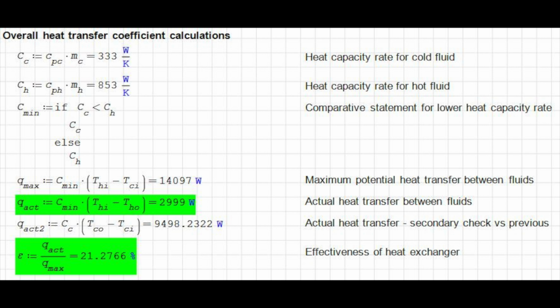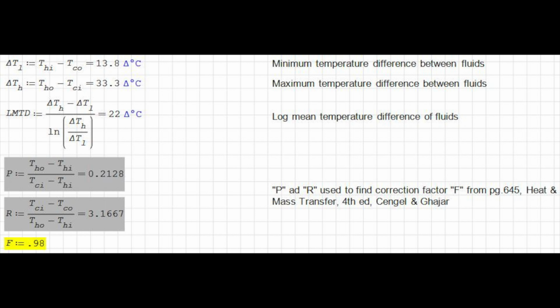So again, this one was operating at 3.33 gallons per minute, which is very, very low when you consider how fast engines actually flow, which is usually in the 10 to 12 gallons per minute range. All right, obviously the cold one takes precedence as the minimum, so it is used down here for calculation. The theoretical maximum that could be pulled out is 14,000 watts or 14 kilowatts. The actual that was pulled out was 3 kilowatts. So that gives us an effectiveness of Q actual over Q max, 21%. So it is a 21% effective exchanger. Next, we move down to our LMTD calculation. This is where we get the U values.